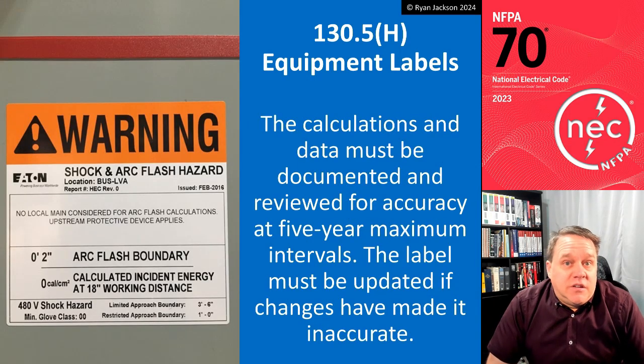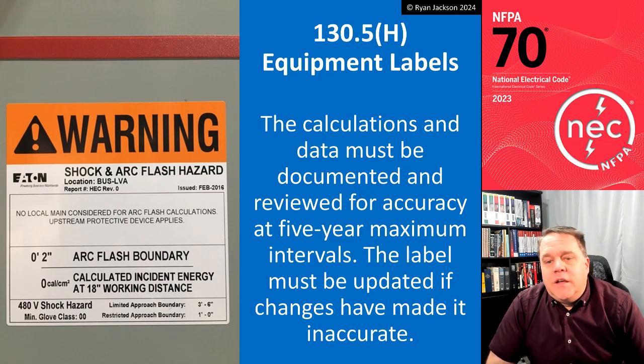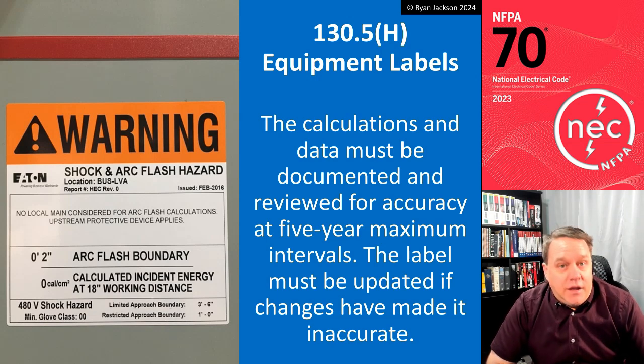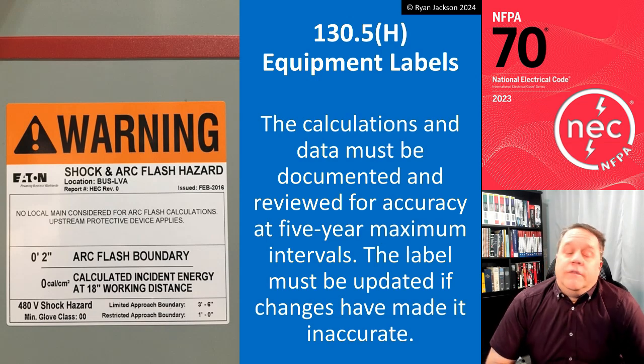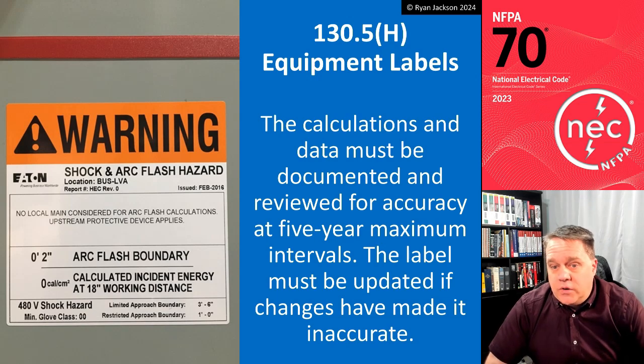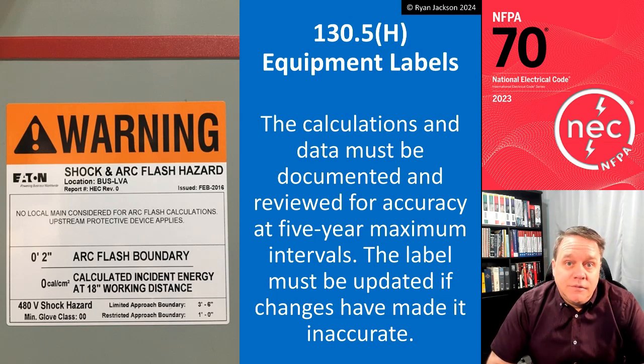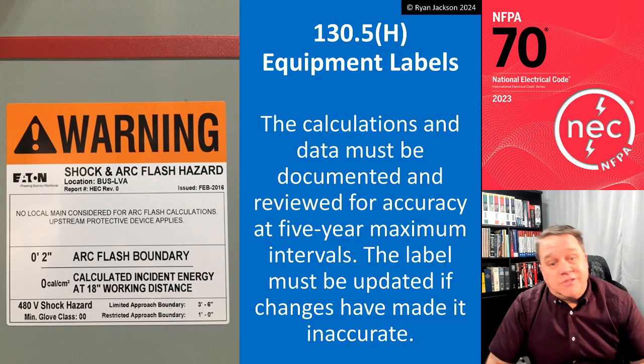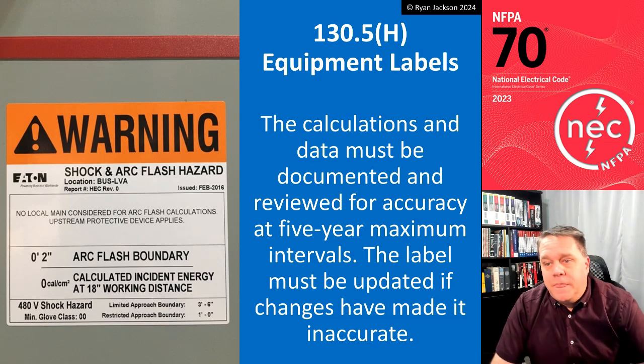The calculations and the data must be documented and reviewed for accuracy at 5-year maximum intervals, and the label has to be updated if changes have made it inaccurate. All right, so review it every 5 years, and if you don't need to update it, then don't update it. But if you do need to update it, well, then you need to update it.